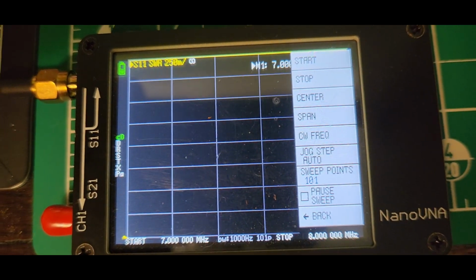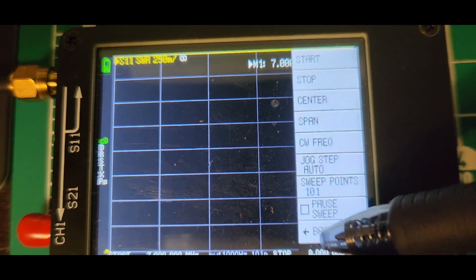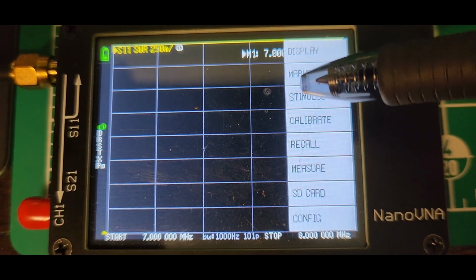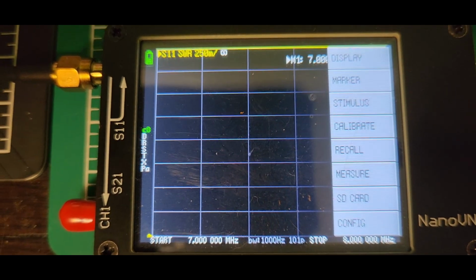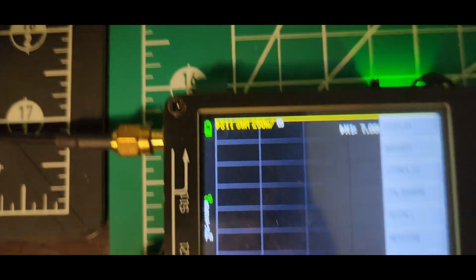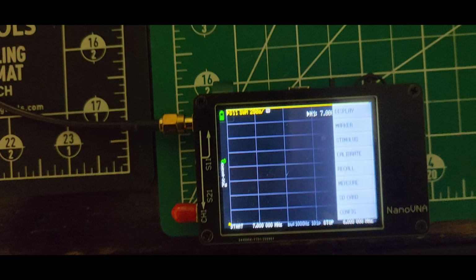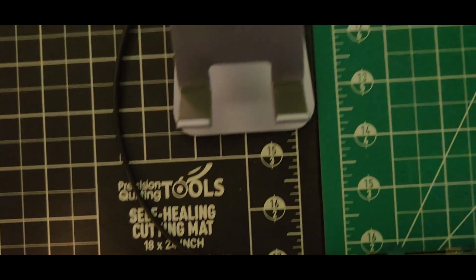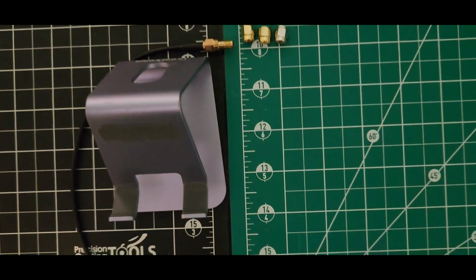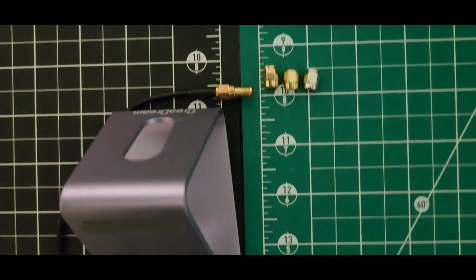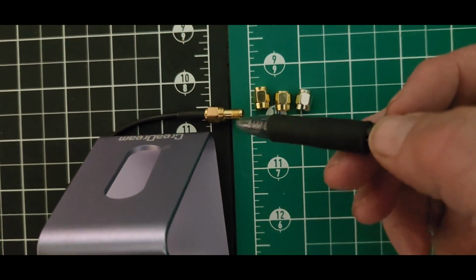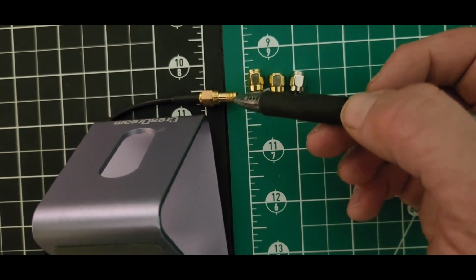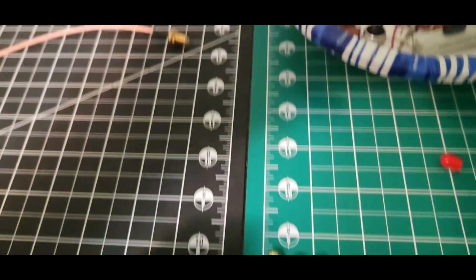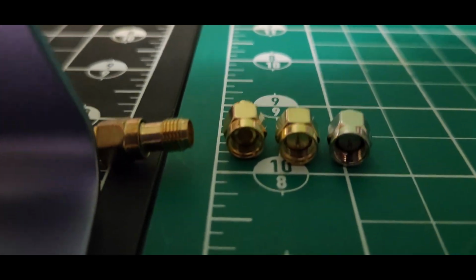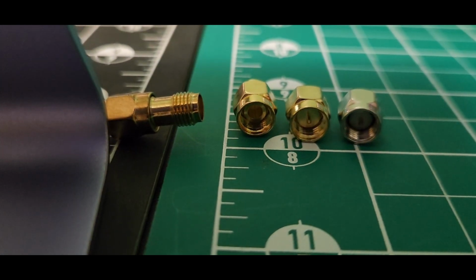So the next thing we're going to want to do is calibrate. And when we do that, we want to do so as close as possible to the device under test. Here I have a jumper. It's about a 12-inch jumper terminated in a male SMA, which I've attached a barrel connector, bullet. And here are the 3 slugs that come with the VNA for calibration.